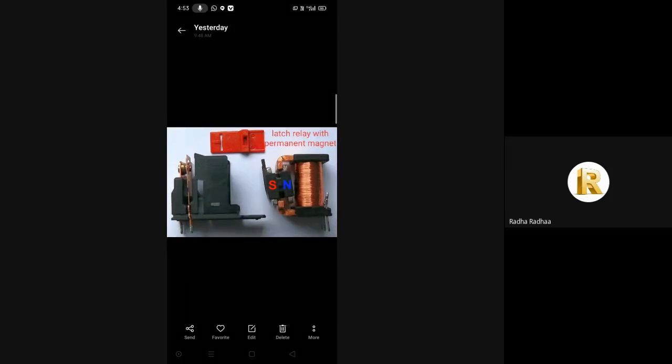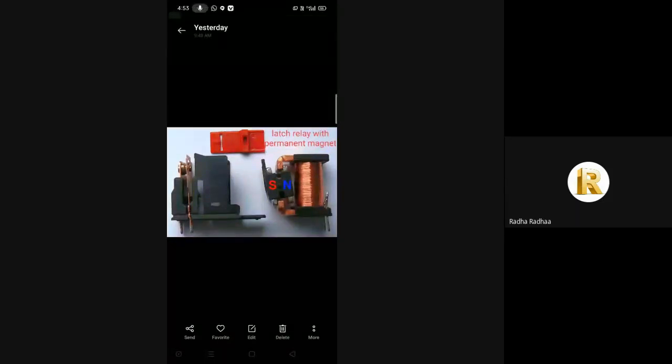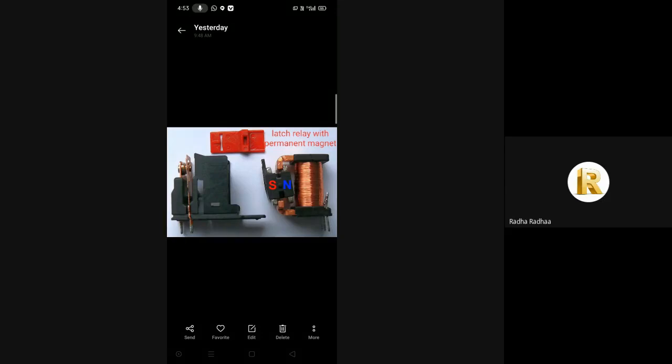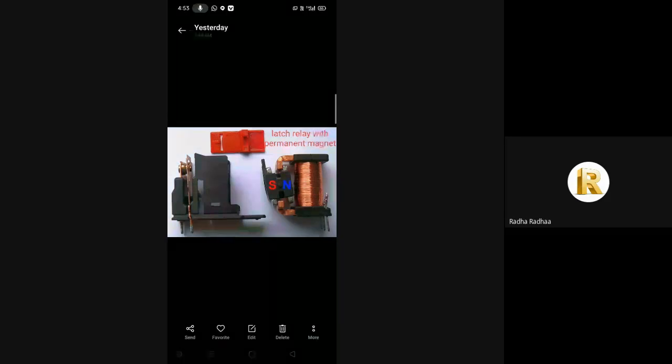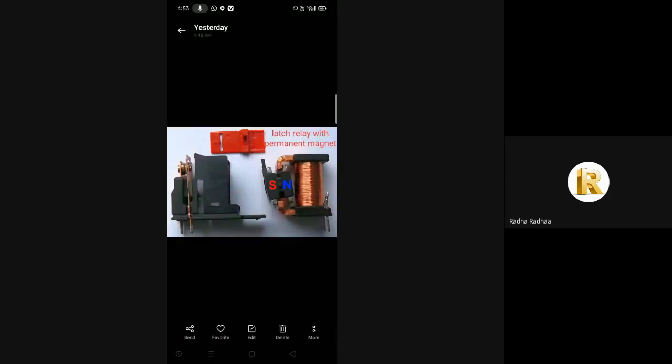A latching relay is a two-position electrically activated switch. It maintains either contact position indefinitely without power applied to the coil. It is controlled by two momentary acting switches or sensors: one sets the relay and the other resets the relay.